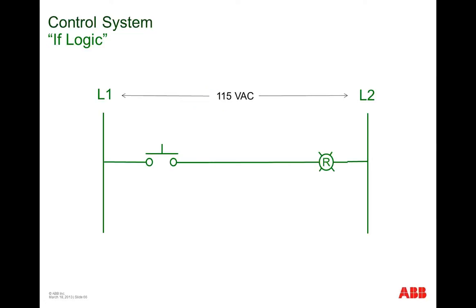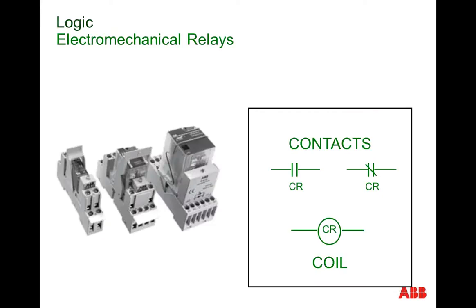This is a fairly simple, what we call relay ladder diagram. It's a circuit diagram, and electricity is going to want to flow from line 1 to line 2, and we form rungs of logic. So we can see here a simple push button, and if I press the push button and hold it, I will conduct power to the red pilot light. This is a very simple if circuit. If push button pressed, red light glows.